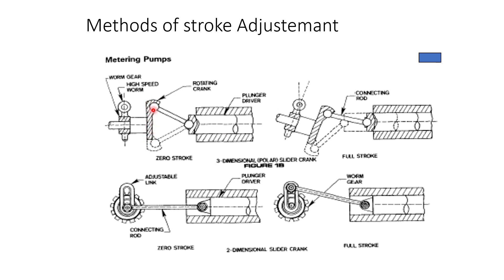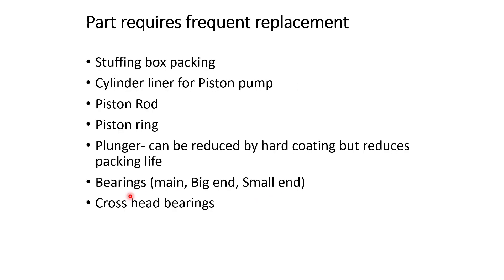Now let us see how the stroke of the pump can be adjusted. There are two methods. In the first method shown at the top, the pin moves in a slot — when it is at the top, the stroke is minimum, and if we move it down, the stroke goes on increasing. In the second method, a rod is moved up or down on the crankshaft. When you move it outward, the length increases and the stroke increases. When you move it inward towards the center, the stroke is lesser.